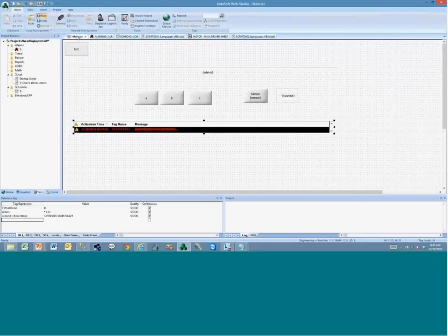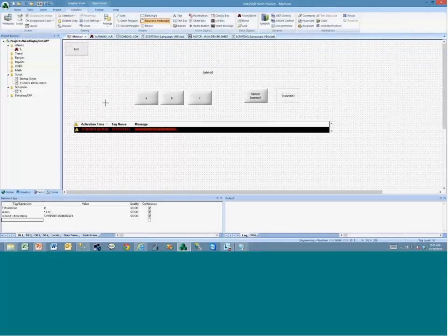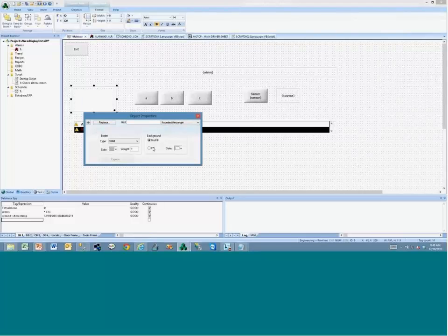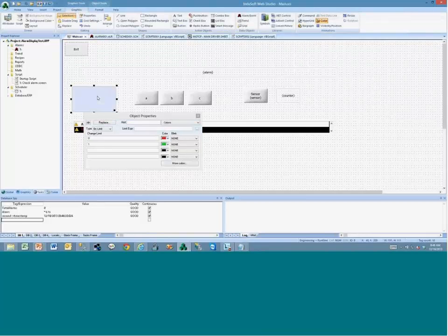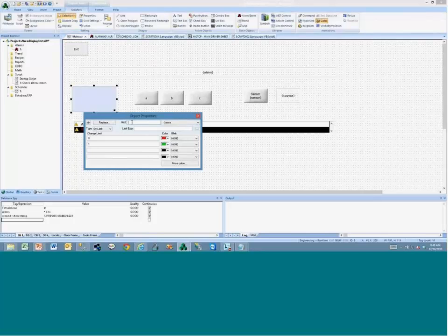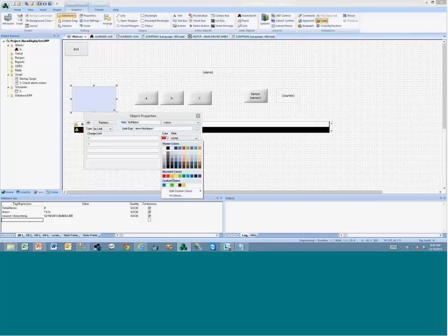Just one quick tip. Usually when customers try to build something like that, a question is how to change the color of the object if the user moves the mouse on the object. So let's say I have a filling color here of a light blue. And when the mouse is on the object, I want to change the color. So here, in any object, you have this hint field where you can write any label, like let's say my ribbon, right? And when you move the mouse on the object during runtime, the value of this hint is written to a system tag called hint. So here in tag expression, you can say if hint is equal to my ribbon, then the expression returns 1, and I want to show it as orange, for example.